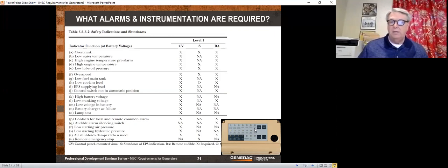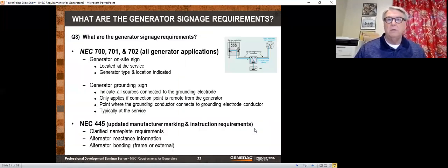And I hate telling people that, but I want to make sure you understand that the generator you purchase must be an industrial generator with an NFPA 110 controller if you want to use it in a legally required or emergency application. If you want to buy one of the light duty commercials, which we sell quite a few of, or a residential generator, no problem, but just don't use it in an emergency or a legally required situation. Okay, I've probably beat that to death.